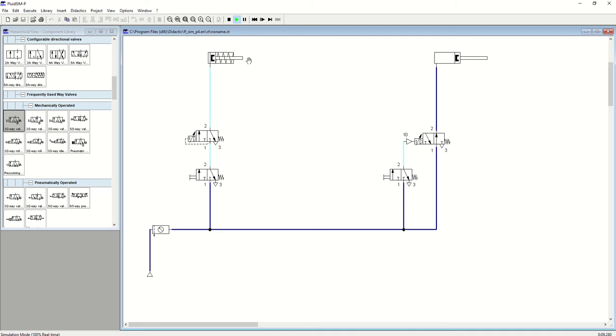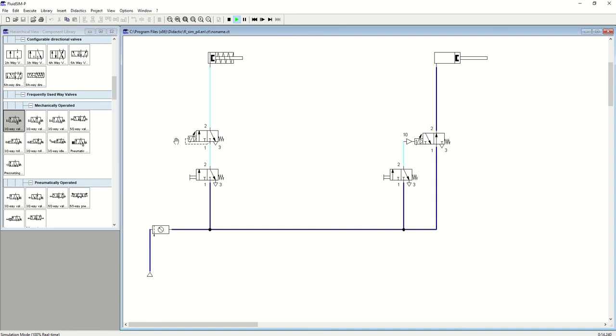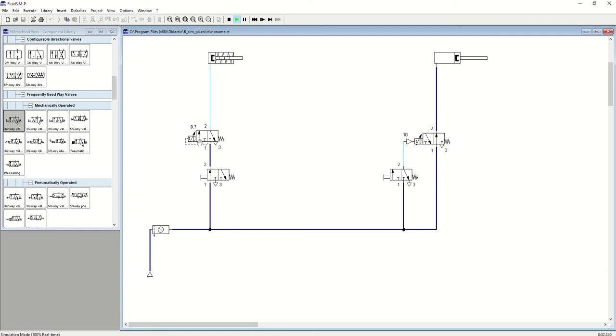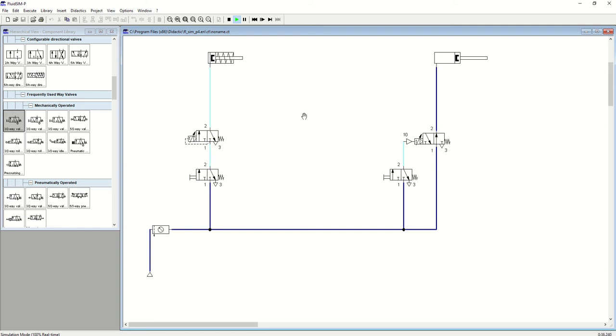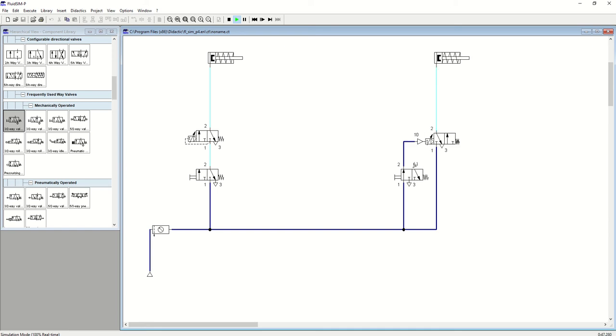This is what's called a normally closed or an on delay timer. What happens is something comes on after a delay. If I push this push button, you have a delay of five seconds, then something comes on - the output comes on. As opposed to an off delay timer, where something comes off after delay. The output is on, there is a delay, and then the output goes off. The two timers work in reverse.